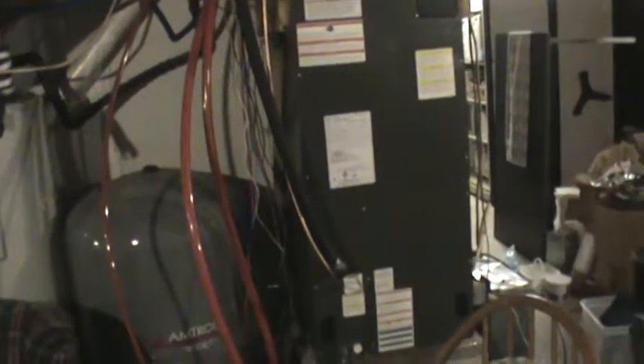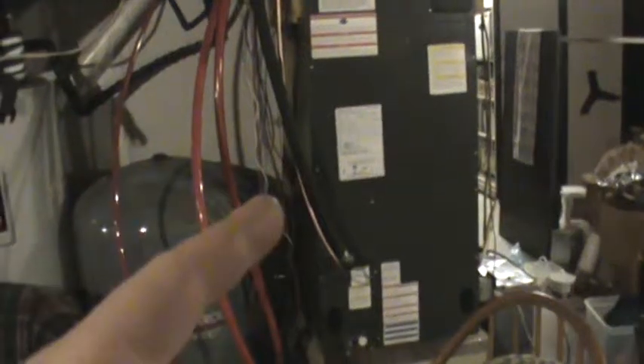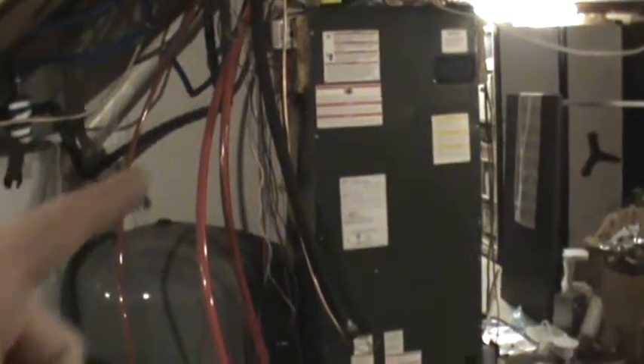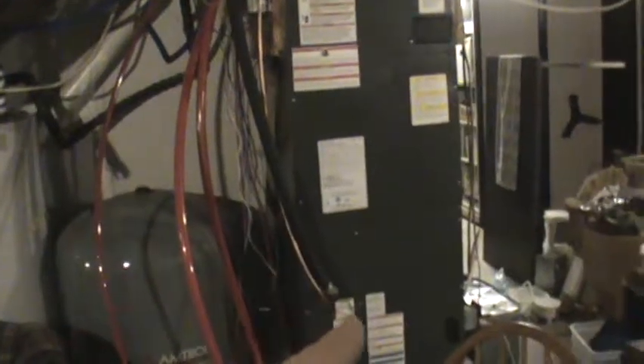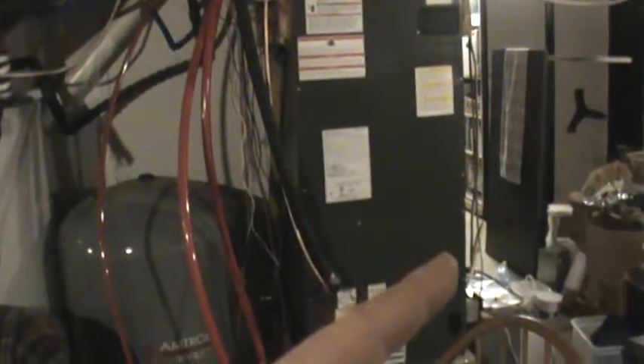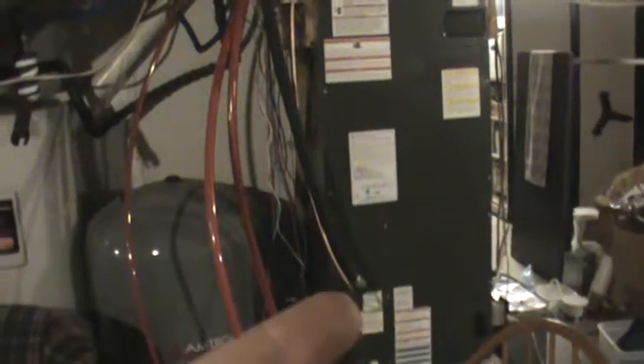You know what? I may be wrong. That may not be the case. I am wrong. The thermostatic expansion valve for heating mode is actually outside in the compressor unit. The thermostatic expansion valve in this unit is for cooling mode, so I'm wrong. So what happens is the superheated gas comes in this black pipe, goes through the A coil, is converted into a liquid, basically losing its latent heat of vaporization, and then goes back up this copper pipe and out to the heat pump unit.